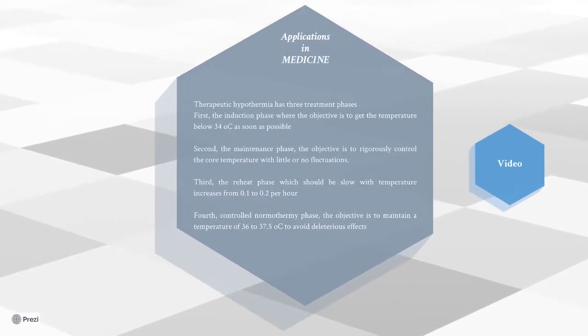Applications in medicine. Therapeutic hypothermia has three treatment phases. First, the induction phase, where the objective is to get the temperature below 34 degrees Celsius as soon as possible. Second, the maintenance phase, the objective is to rigorously control the core temperature with little or no fluctuations. Third, the reheat phase, which should be slow with temperature increase from 0.1 to 0.2 per hour. Fourth, controlled normothermic phase, the objective is to maintain a temperature of 36 to 37.5 degrees Celsius to avoid deleterious effects.